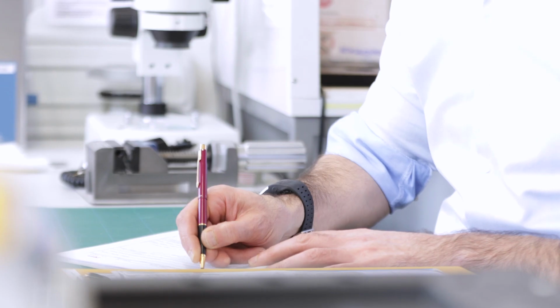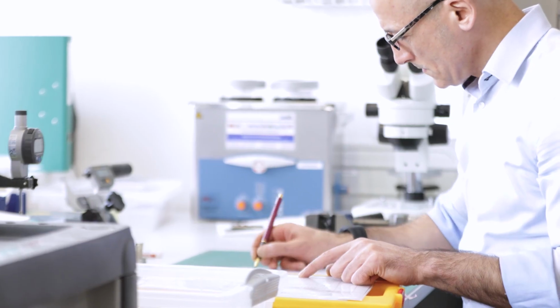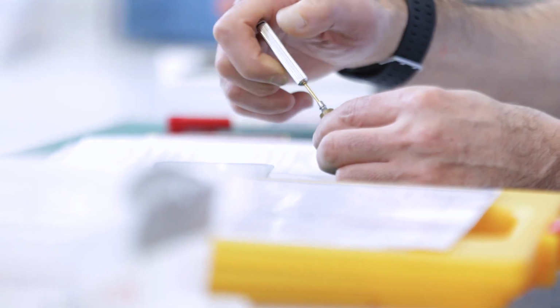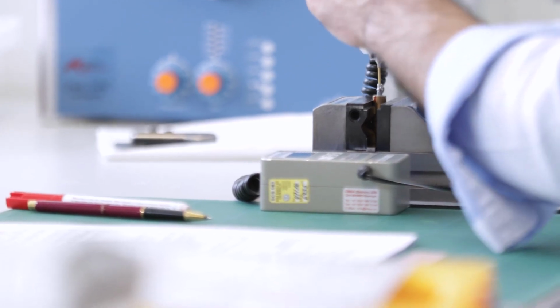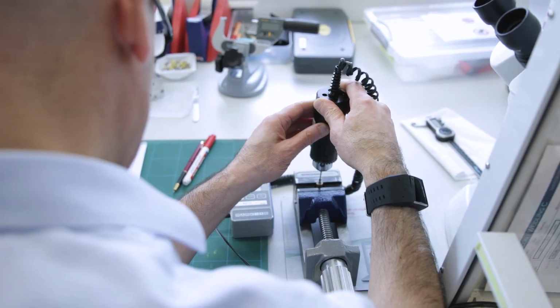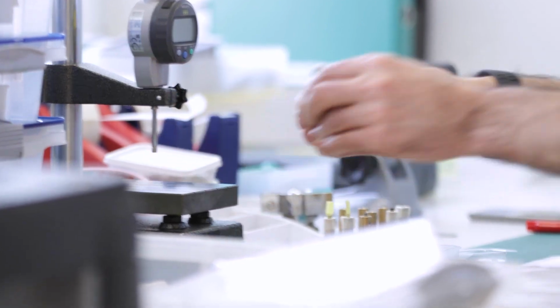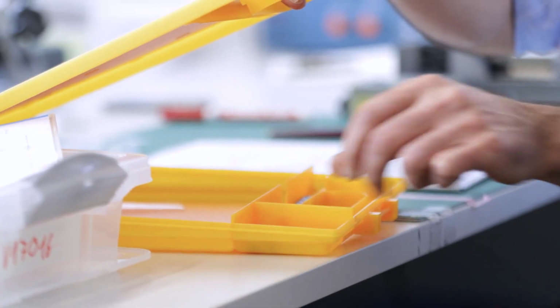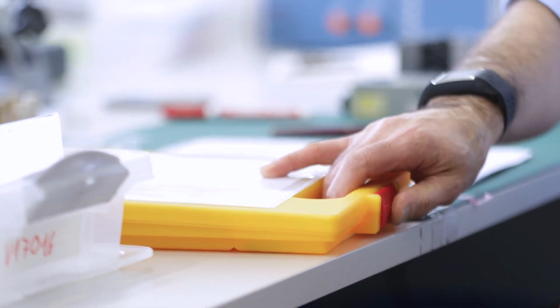The parts are assembled and the screws are tightened according to the instruction for use. The screws are tightened with a digital torque sensor in order to assure accuracy and reproducibility. The specimens are placed in the holding device, representing the load situation according to ISO 14801 standard.